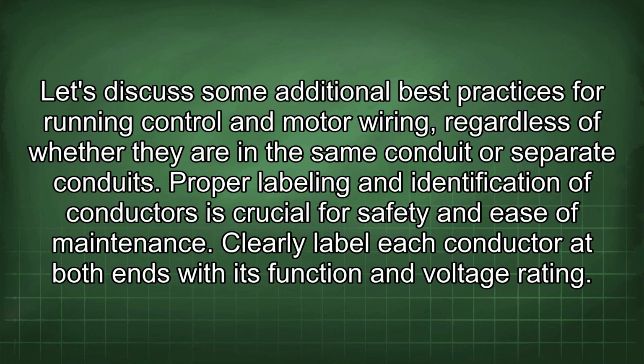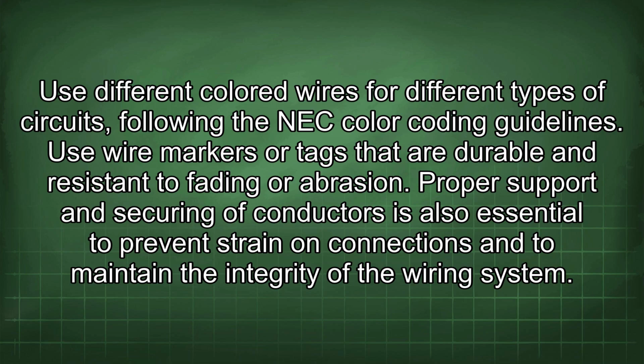Let's discuss some additional best practices for running control and motor wiring, regardless of whether they are in the same conduit or separate conduits. Proper labeling and identification of conductors is crucial for safety and ease of maintenance. Clearly label each conductor at both ends with its function and voltage rating. Use different colored wires for different types of circuits, following the NEC color coding guidelines. Use wire markers or tags that are durable and resistant to fading or abrasion. Proper support and securing of conductors is also essential to prevent strain on connections and to maintain the integrity of the wiring system.